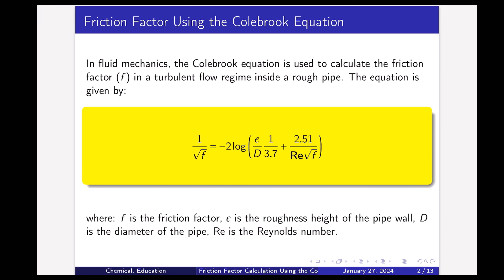The equation is given by 1 over √f = −2 log(ε/d × 1/3.7 + 2.51/(Re√f)), where f is the friction factor, ε is the roughness height of the pipe wall, d is the diameter of the pipe, and Re is the Reynolds number.